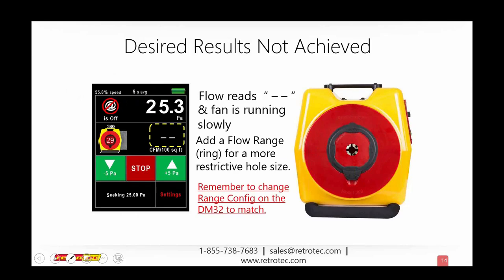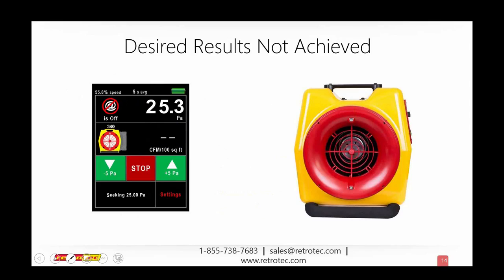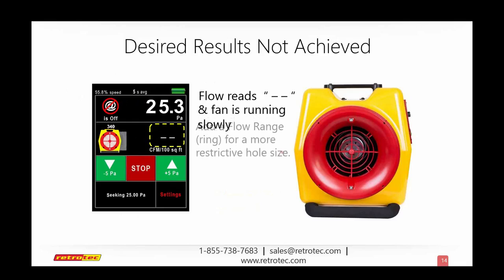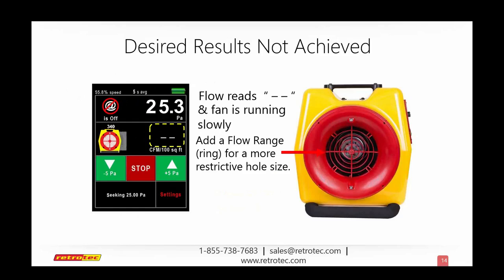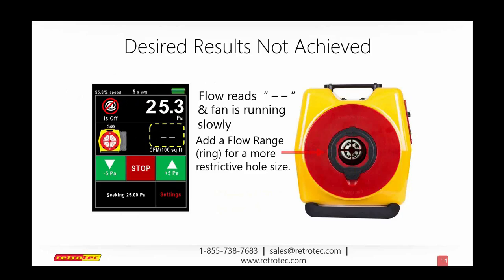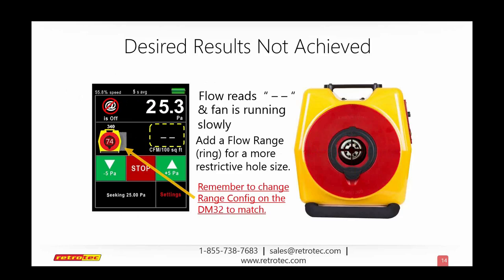So the point is that I've added, and I'll show you again in the little schematic here, we started with an open range and there wasn't enough flow to get a reading. So what we've done here is add a more restrictive range, a plug, that's going to make a smaller known hole for us to compare with the leakage, and also take that very small volume of air and concentrate it through the fan so that we can get a nice reading. So hopefully that makes sense. I'm going to move on.